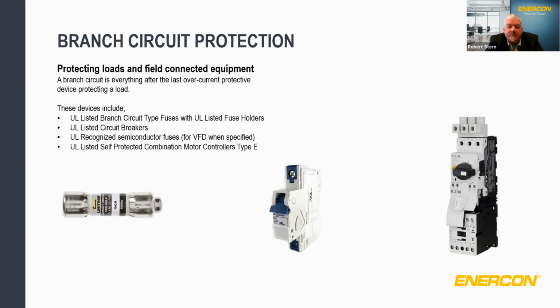So, branch circuit protection. A branch circuit is everything after the last overcurrent protective device protecting a load. To ensure a load is protected from damage from short circuit and potential damage from incoming supply voltage, the appropriate disconnect is used from the feeder lines to the circuit, and this is considered to be a class one circuit. This is a power providing circuit. The types of devices that UL allows in this feeder or branch circuit protection are UL listed branch circuit type fuses with UL listed fuse holders, UL listed circuit breakers, UL recognized semiconductor fuses, but only when used with VFDs where they're specified, and UL listed self-protected combination motor controllers of the type E variation.